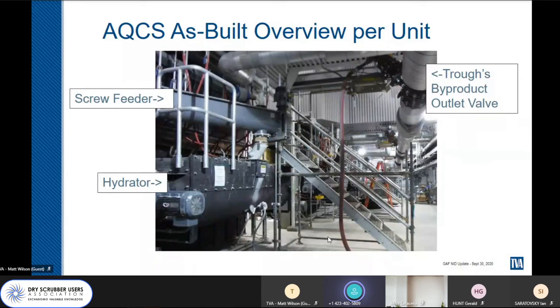So what's out of the picture is one mixer per module, one J-duct mid-reactor, which we've already gone over well, one activated carbon injection lance per module, one long fluidizing trough with that one byproduct valve. That fluidizing trough is slightly tilted towards the hydrator mixer side. And we put warm air up through the bottom of a fluidizing air cloth. In general, we do not have any issues with moving that fluidized byproduct. It tends to feed well out of the single outlet valve, and out to the 4-meter wide recycle rotary feeder. The recycle rotary feeder is how we meter the recycle product rate back to the mixer.